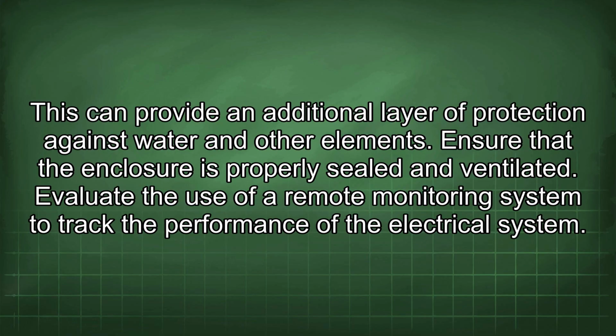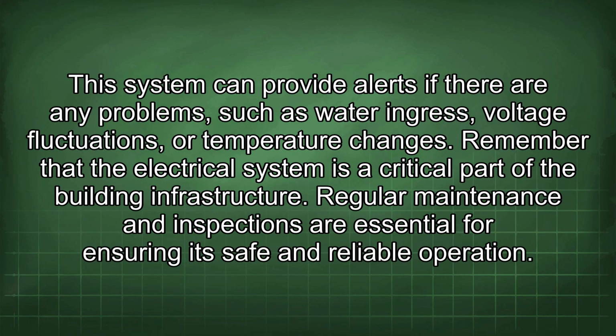This can provide an additional layer of protection against water and other elements. Ensure that the enclosure is properly sealed and ventilated. Evaluate the use of a remote monitoring system to track the performance of the electrical system. This system can provide alerts if there are any problems such as water ingress, voltage fluctuations, or temperature changes.